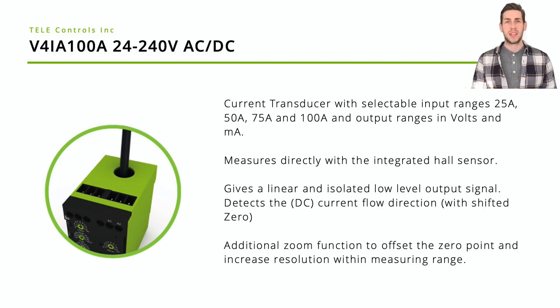The 100 in the type code describes the 100 amp AC and DC measuring range that we can cover with this item. You can select from a 25, 50, 75, or 100 amp range in one device. The nice thing about this product is it also has an integrated Hall sensor, which makes it unnecessary to have additional current sensors to hook up to your transducer.